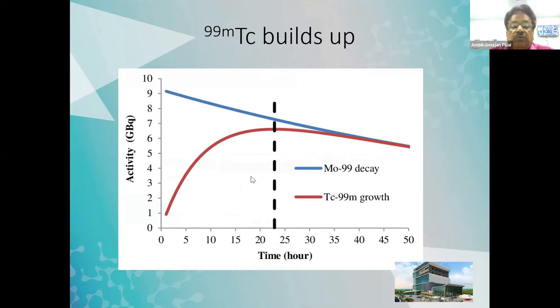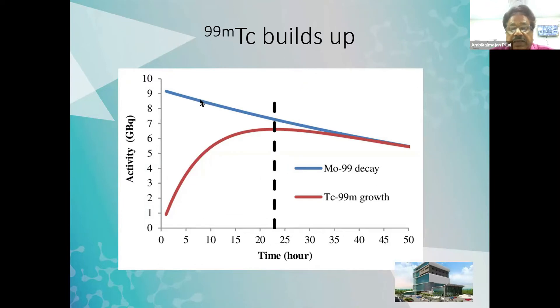If you buy a generator — a one-curie generator — this is how the activity will be reducing. As time passes, the molybdenum activity will keep on reducing. After about 50 hours, that is about two days, it will be only about 50 to 60% of the original activity.